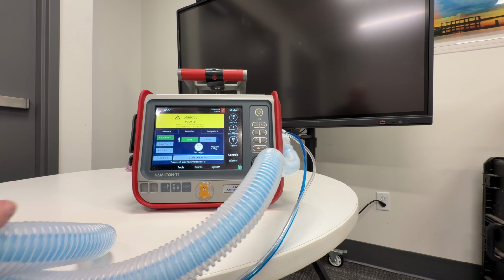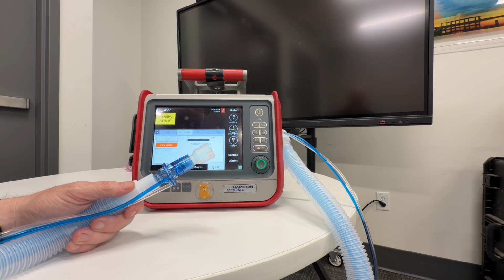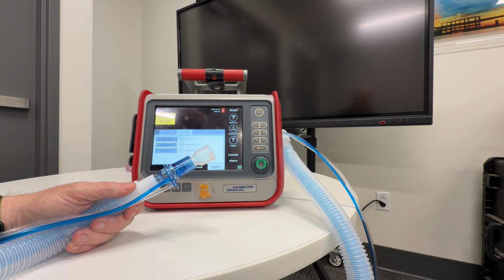You're going to hear this thing start to ramp up, and when you start hearing it ramp up, and it continues to escalate, that's a good sign. That means that as long as you pay attention to what you're doing, it's going to take just a second, it's going to pass. It says turn the flow sensor. We're going to take the entire thing off and flip it again. It's going to go through the same process of a ramp up, and it's testing the flow through that sensor. Green is good. We check that box, so that means that we have done our proper check.